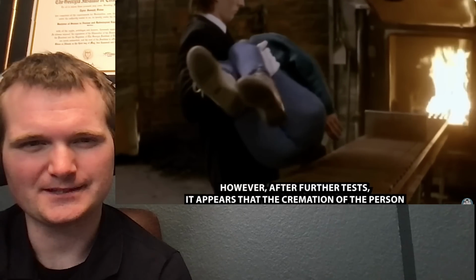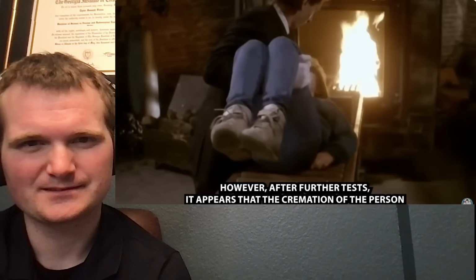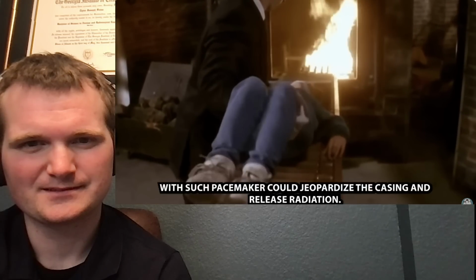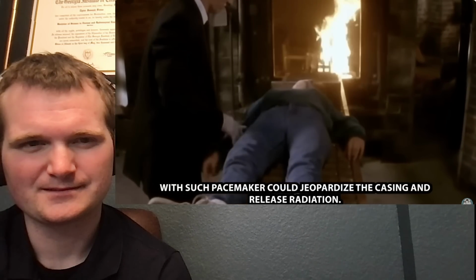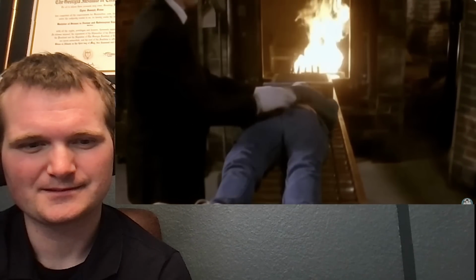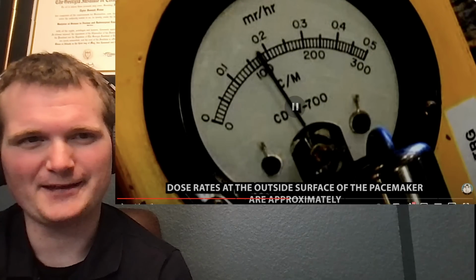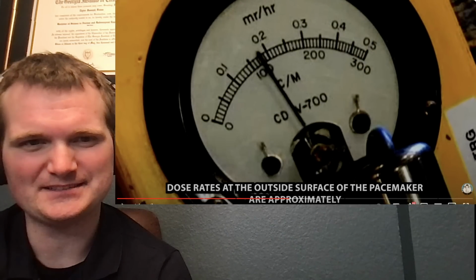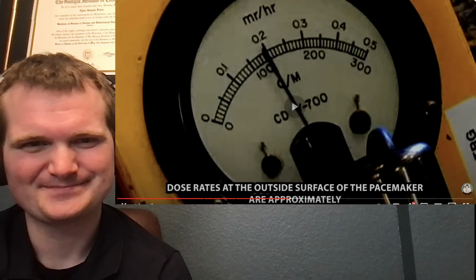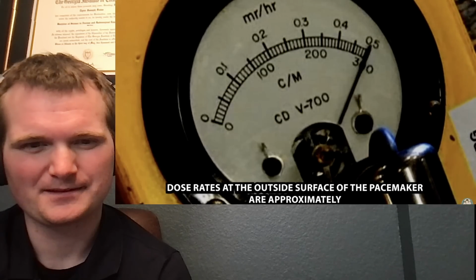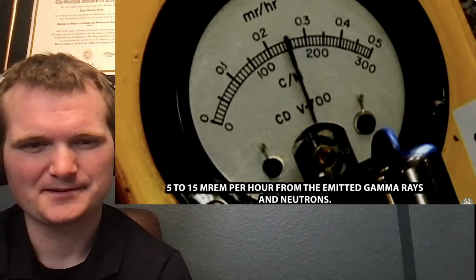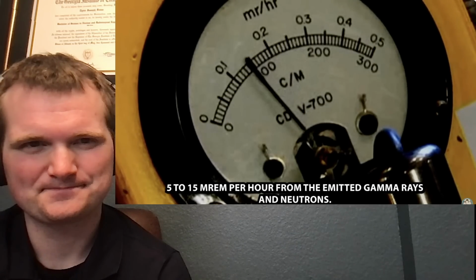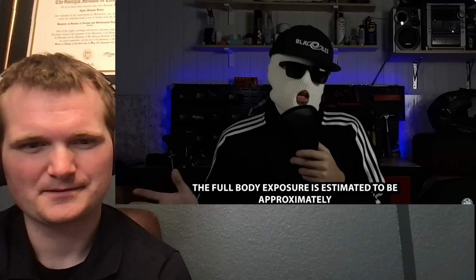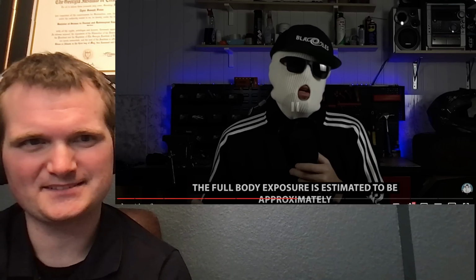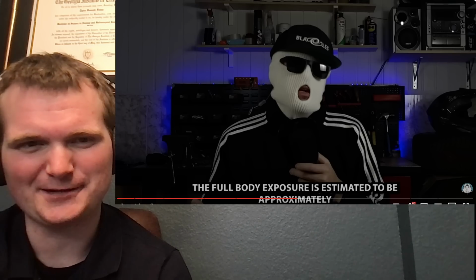However, after further tests, it appeared that cremation of a person with such a pacemaker could jeopardize the casing and release radiation. Oh, that'd be something - you get a nasty surprise on cremation. Wow. Radiation rates at the outside surface of the pacemaker are approximately 5 to 15 millirem per hour from the emitted gamma rays and neutrons. The whole body exposure is estimated... that's not very much, but it's one of those things that adds up over time.